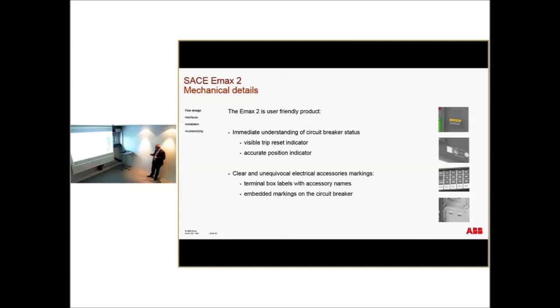Some small improvements, but also important. You have a clear trip indication. You have a clearer indication of the position of the breaker: is it inserted, in the test position, or in the withdrawn position. You have the push button that gives the stop when you arrive at the position you require.